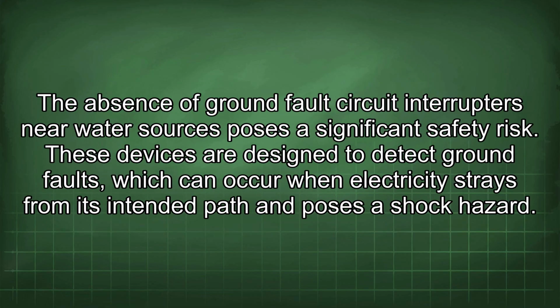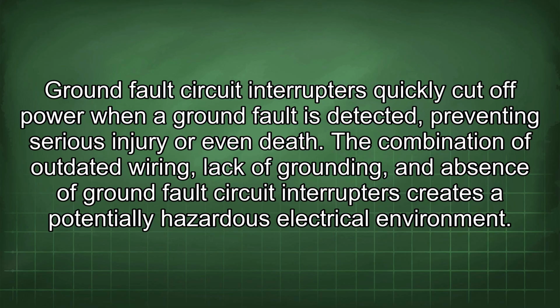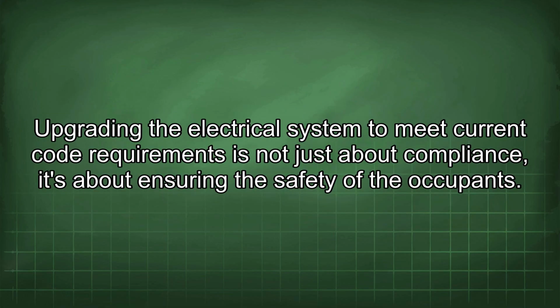The absence of ground fault circuit interrupters near water sources poses a significant safety risk. These devices are designed to detect ground faults, which can occur when electricity strays from its intended path and poses a shock hazard. Ground fault circuit interrupters quickly cut off power when a ground fault is detected, preventing serious injury or even death. The combination of outdated wiring, lack of grounding, and absence of ground fault circuit interrupters creates a potentially hazardous electrical environment. Upgrading the electrical system to meet current code requirements is not just about compliance, it's about ensuring the safety of the occupants.